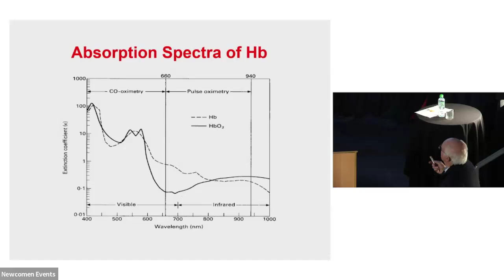The initial pulse oximeter was an analog device, and fortunately with an analog device you could actually make a sensor which, because of its filter, could look at an isobestic point, which it did. The device they used was a halogen lamp here with a filter reducing some of the wavelengths, and glass fibre here. And so the signal came through here and went this way and that way. The unfortunate thing about it was that it was very difficult to make the glass fibre things in 1970, a bit later, 1972-ish. And not only that, because it was a halogen lamp, it used to burn the finger, which wasn't very good for you.